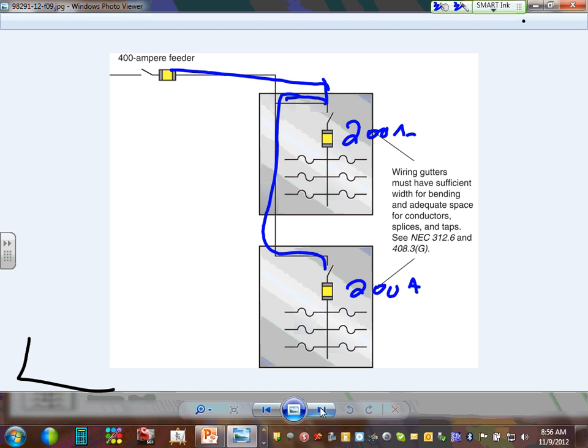What's the advantage of this? The advantage is you have two taps. Where would you use something like this? If you ran out of receptacle circuits and you need more circuit breakers, that's a good application. You have a lighting panel and you ran out of spaces in it. That's a good application, guys, for subfeeding. Can I have thumbs up, guys, about subfeeding?